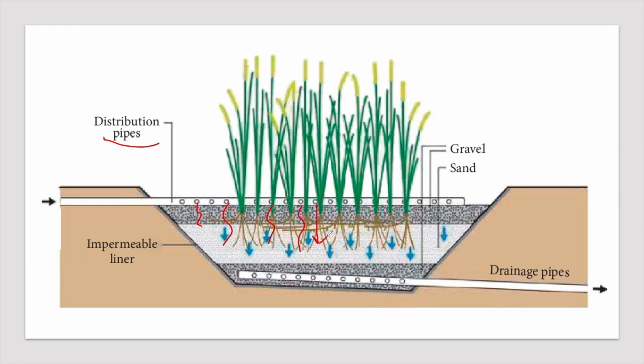Unlike the horizontal flow constructed wetland where flow moves horizontally, here we have a vertical flow of wastewater treated through the media and by the rhizomes of the reeds. The treated water is then collected through the drainage pipes and can be safely disposed if it meets local regulations, or further treated through tertiary treatment such as UV treatment or chlorination.